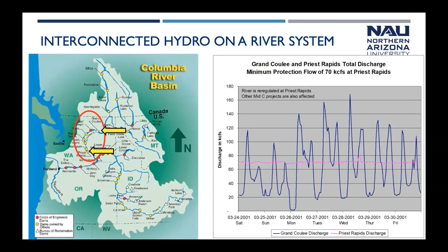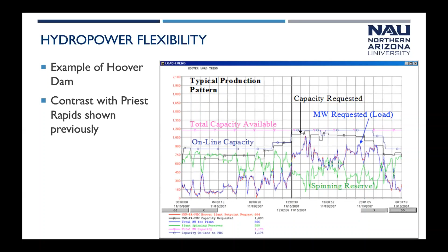Here's an example of Hoover Hydropower from 2007, from their SCADA system. This pink line shows the total capacity available—about 1,200 megawatts that day. What was online and ready to generate was a little under 900, so the difference between online and total capacity is what we'd call non-spinning reserve. The blue line going up and down shows the actual generation, moving quite a bit, so there's some flexibility in what it produces that day. The green line shows the spinning reserve, the difference between online capacity and what's actually being produced—that's a reserve available to use on the system. That's flexibility, a very big contrast with Priest Rapids.